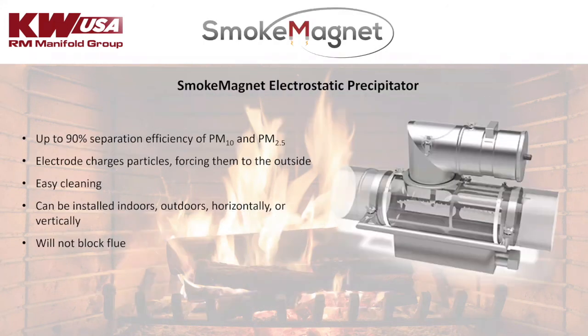So there is a new product that recently came out in Germany. The Smoke Magnet Electrostatic Precipitator. Basically, this little product here is very effective at separating your fine and ultrafine dust particles out of the flue. It's about 90% effective. The way it works is there's a little electrode in there. This is kind of a cutaway picture. There's an electrode in there that charges these particles and forces them to the outside of the housing, and you can knock them down and collect them in that little collection box at the bottom. So it's very easy to clean. They can be installed indoors, outdoors, horizontally, vertically, and they will not ever block your flue.